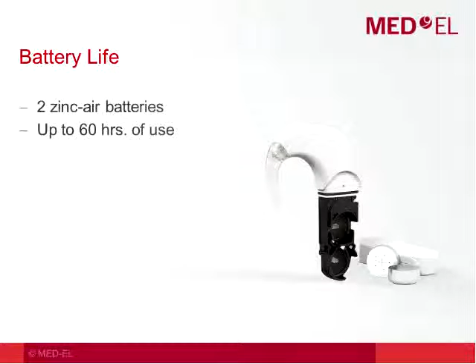We have a number of troubleshooting tools to help you verify that all of your equipment is working the way that it's supposed to. The SONNET audio processor has a multicolor indicator light on it. It can show red lights and green lights, and you might guess that red lights are telling you that there might be a problem or an error, and green lights, of course, are good. So they're usually telling you that everything is working correctly with your equipment.